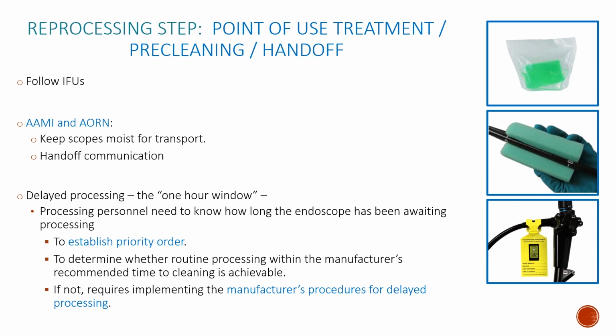Pre-cleaning point of use treatment always occurs right after the procedure in the procedure room at the bedside. It includes actual pre-cleaning, but it also includes removal of accessories, preparation for transport, and communication to processing personnel. All organizations reinforce the need to follow the IFUs for point of use treatment. AAMI and AORN call for keeping scopes moist for transport to keep bioburden from drying. This isn't a new concept related to surgical instruments, but it is a new mentality and expectation related to flexible endoscopes. AAMI and AORN also identify the need for handoff communication to identify the time that point of use pre-cleaning was performed. And that's because time is critical. We need to limit bioburden before it has a chance to dry. Follow the endoscope manufacturer's IFU related to delayed processing protocols.